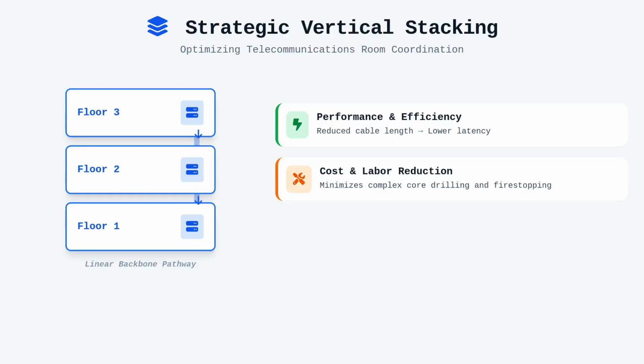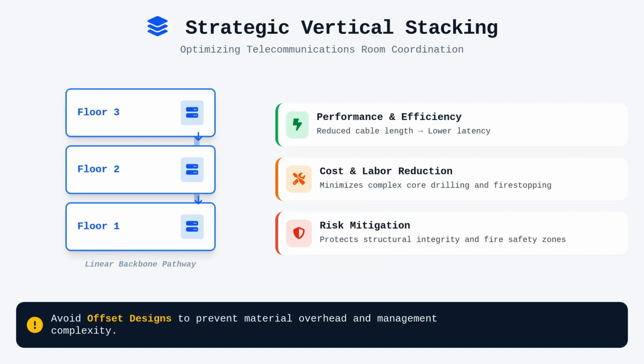More importantly, this alignment minimizes the complexity and associated costs of core drilling and subsequent fire-stopping procedures. Each core penetration through a floor slab is a potential weak point for fire safety and structural integrity. So consolidating these penetrations into a vertically aligned stack is an exercise in both efficiency and risk mitigation. If you find yourself designing a building where vertical alignment is impossible due to architectural constraints, you are essentially forced into a more expensive offset design that complicates cable management and increases material overhead. This is why professional designers prioritize location stacking early in the schematic phase of building design to avoid these technical hurdles later in the construction process.